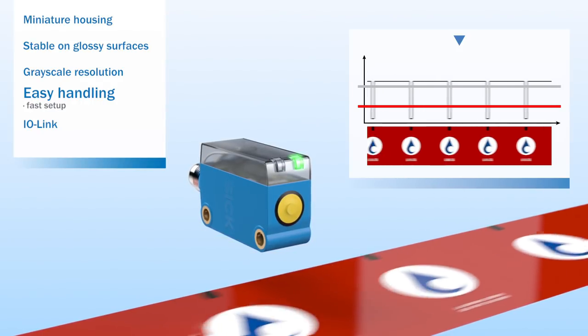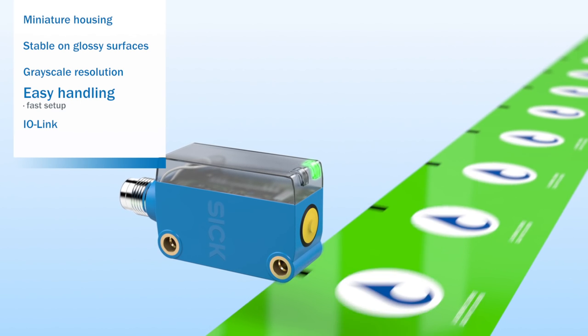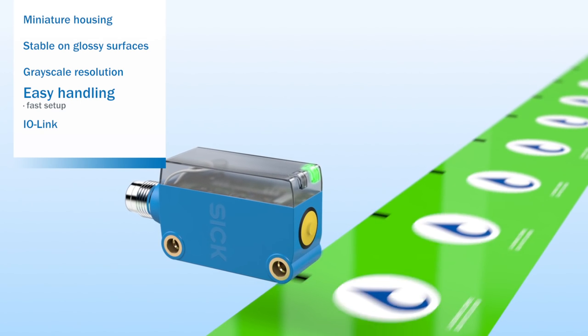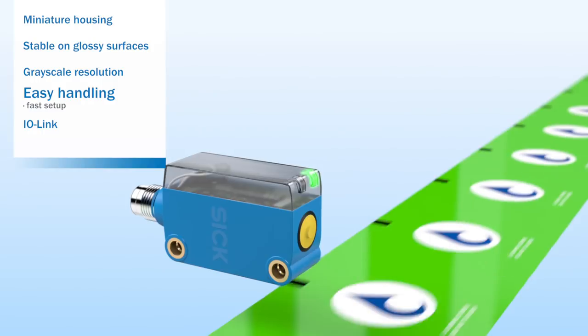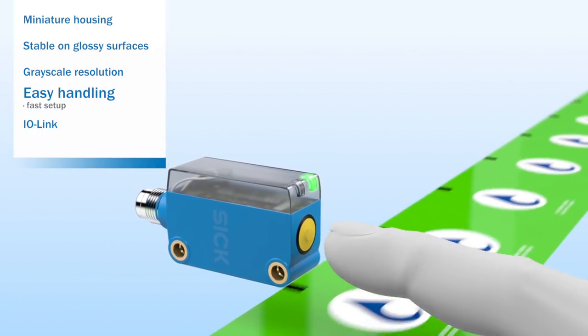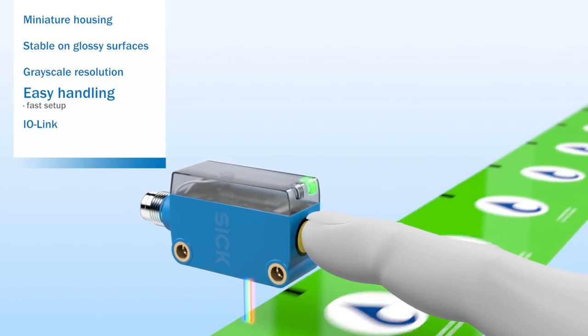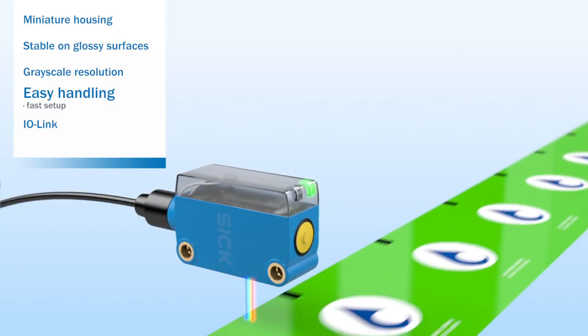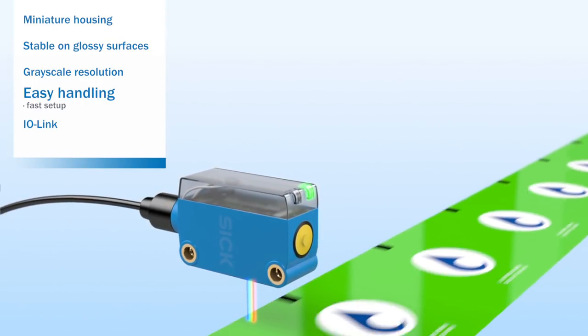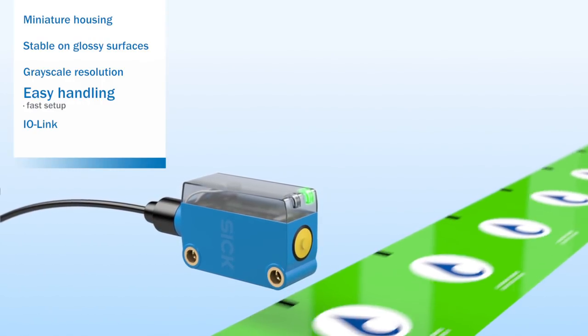Supplementary to these static methods, dynamic teach-in of materials is also supported. If the push button is pressed and held down while the material is running or a signal is sent via the control cable, the KTM will capture the differences in brightness between background and mark.